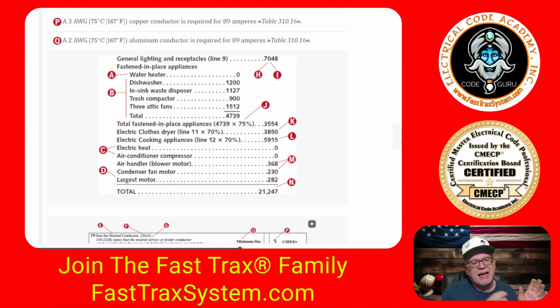If you remember back in the regular method under Part 3, standard method we like to call it, that when you have 4 or more fastened in place appliances, that you get to take a demand of what? 75%. So you would just add them all up, multiply it by 75%, and that's what you'd use, right? So the big question that people ask, like, okay, when I'm doing the neutral, do I do the same thing? And the answer is absolutely. If I've got 4 or more fastened in place appliances that have a neutral contribution, that would be any of them that are 120 or 115 in your list, okay, excluding all of those that are 240, okay?